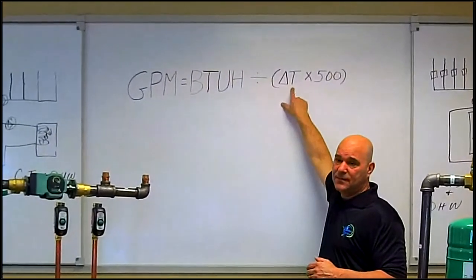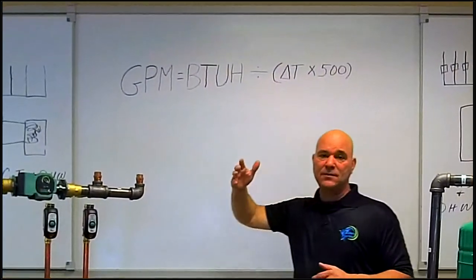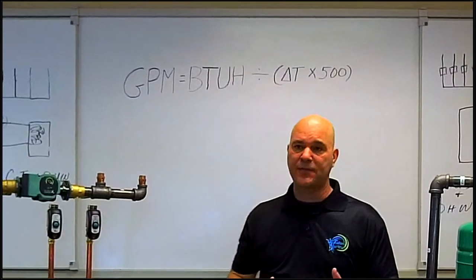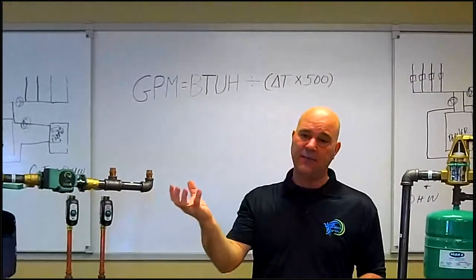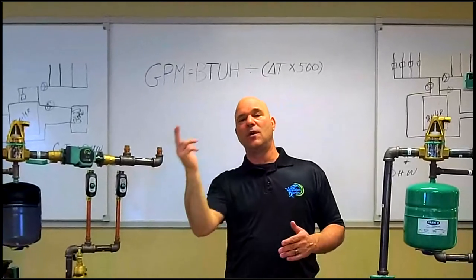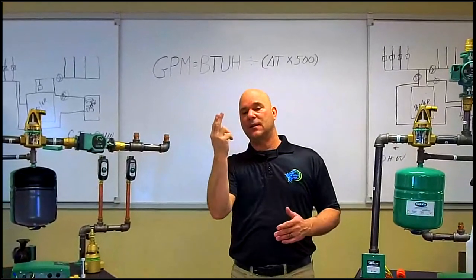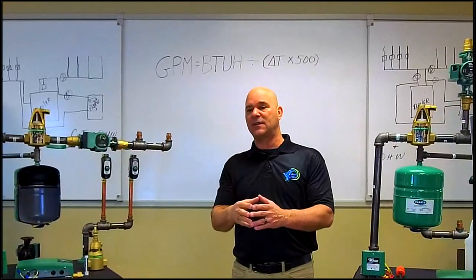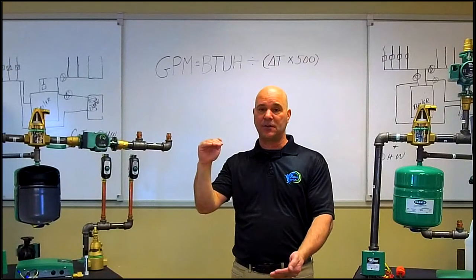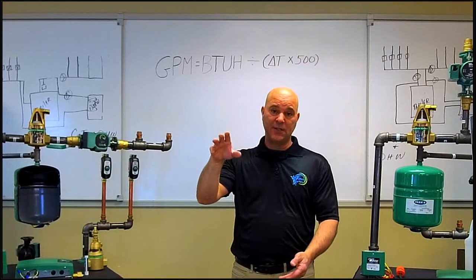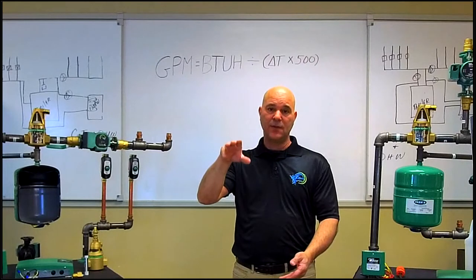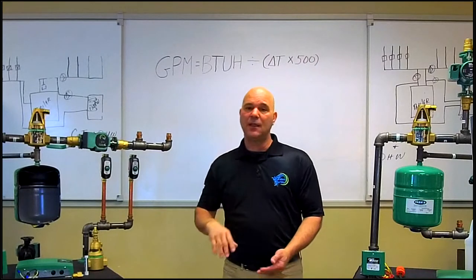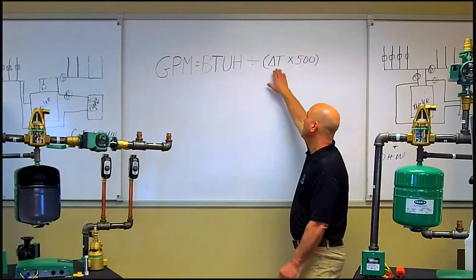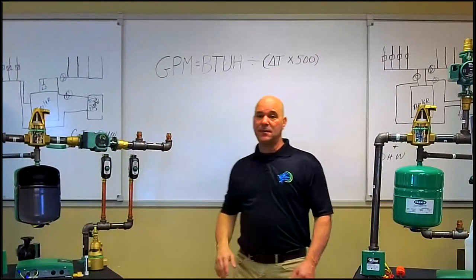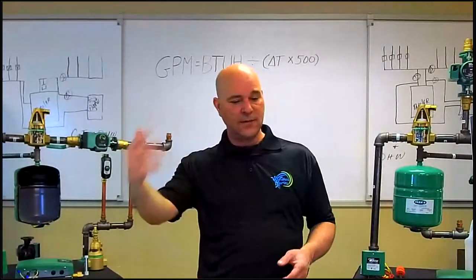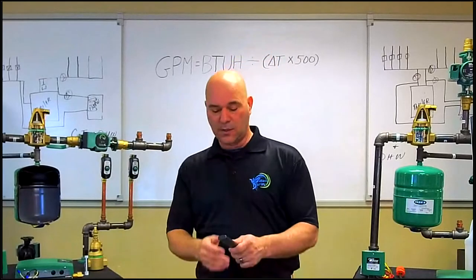This is delta T. That's temperature differential. What we mean by temperature differential is we're going to have a temperature leaving the boiler. It's going to go out through the heat emitters, out through the heat circuit. It's going to come back to the boiler, and it's going to be at a different temperature because we just gave off the energy in that space through the heat emitters. That is a delta T. That's going to be something you need to know as we're going forward, because we're going to harp on that.